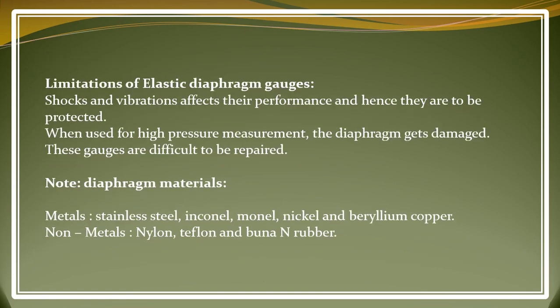Now let's talk about limitation of elastic diaphragm gauges. Shock and vibration affects their performance, and hence they are to be protected. As you can understand, when the shock is applied or a vibration is applied, the diaphragm is also deformed, so the output can be affected. So we have to protect it from the vibration or shock.